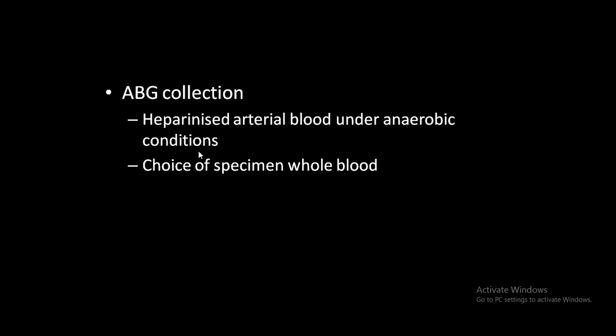Transport of the sample is also a crucial point in arterial blood gas analysis. ABG parameter values will be affected if they are not transported properly. So they should be put on an ice pack or immersed in ice water slurry if any delay is expected in analysis of the arterial blood gas sample. The guideline says as soon as the blood is collected, it should be analyzed immediately on the ABG machine. But if there is some kind of expected delay, you must put it on ice water slurry or ice pack.